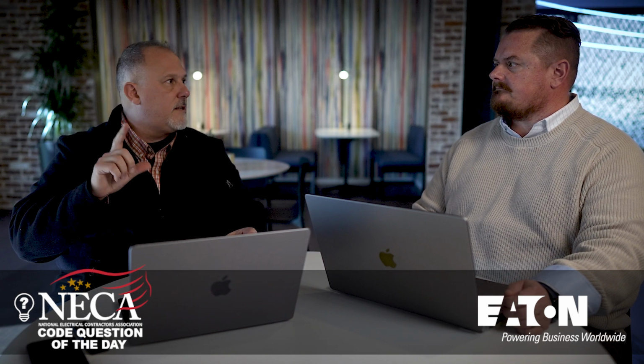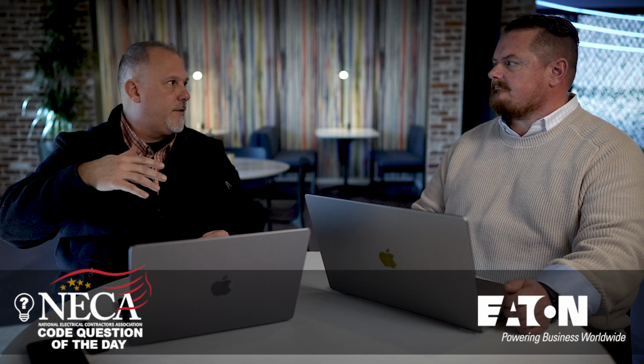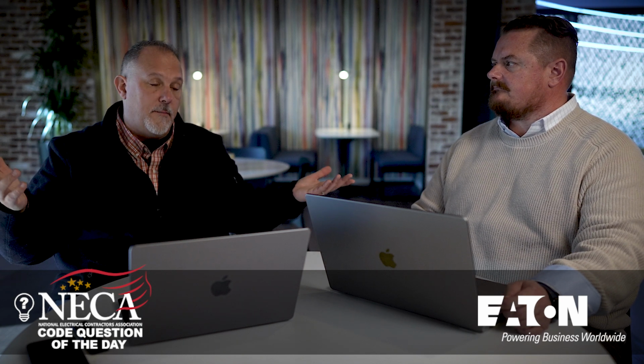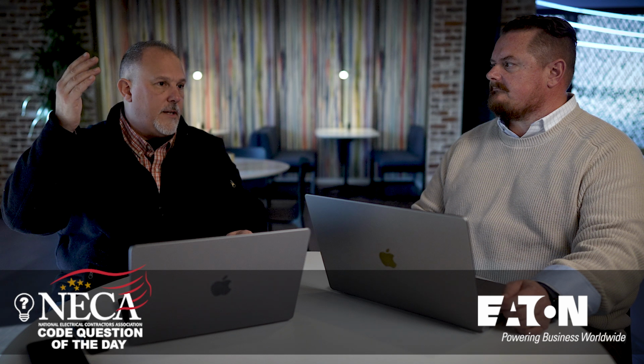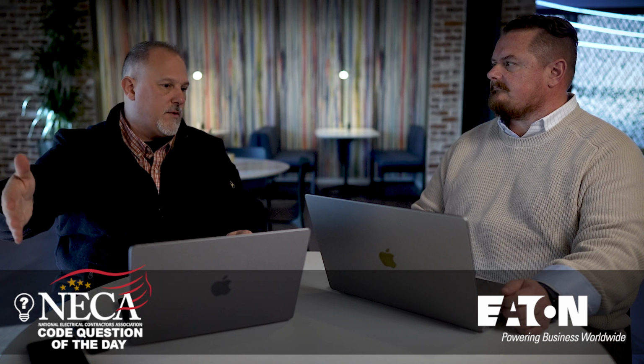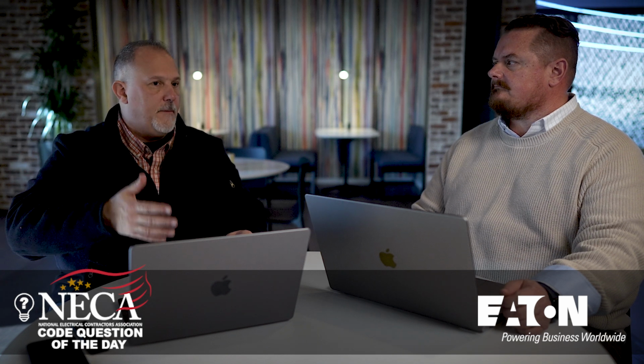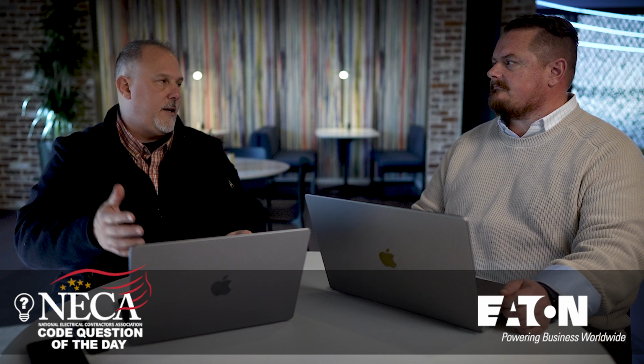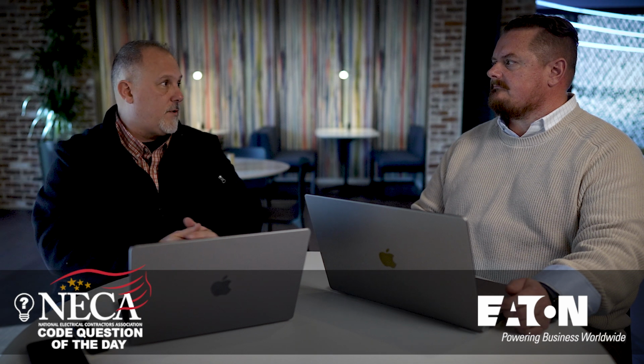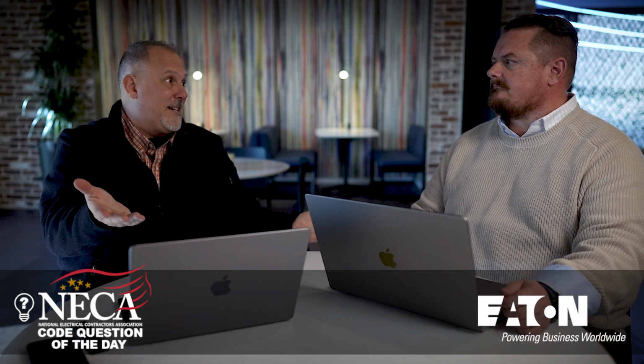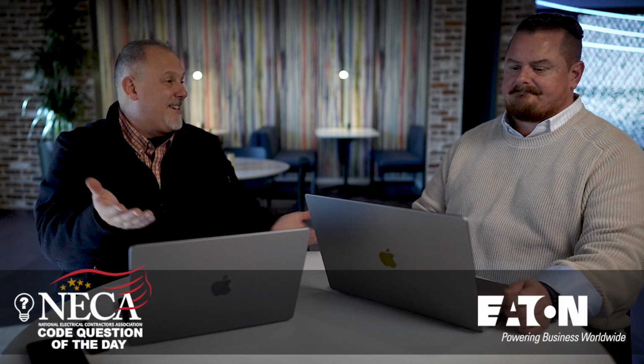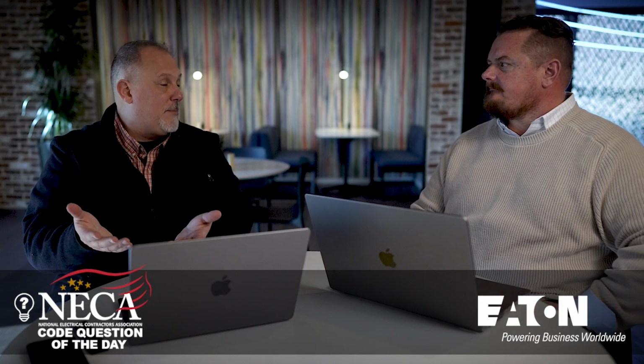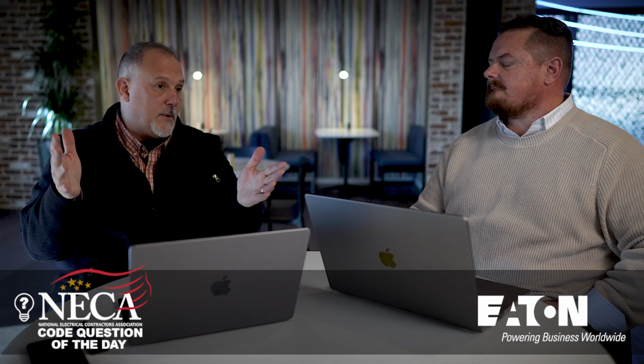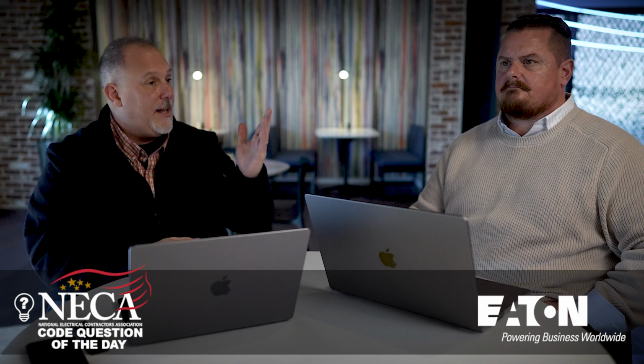minus taking the time, which they put on the agenda for the budget, right? Because we all live on budgets. He says, minus putting a 1-to-1 transformer in front of it to knock it down, they put a fusible disconnect in front of it and then planned to put that transformer. Because I said, you're going to need secondary protection anyway, right? I said, so you're not wasting money by buying a fusible disconnect that you can put multiple different types of fuses in front of it. So it is an option.